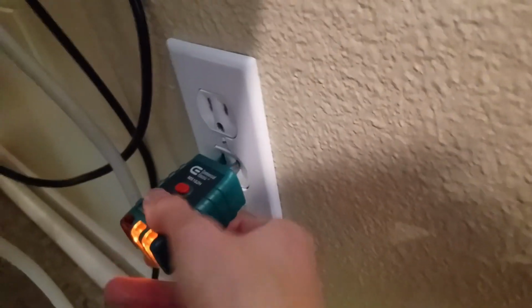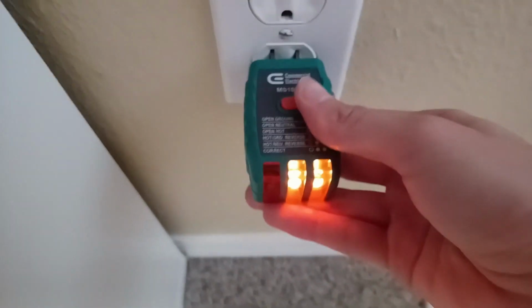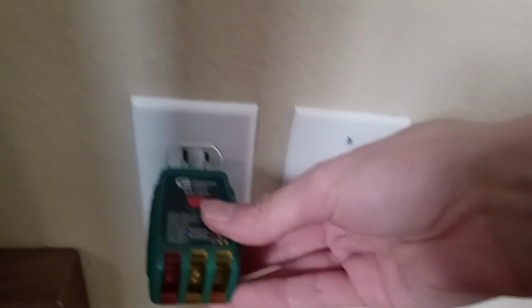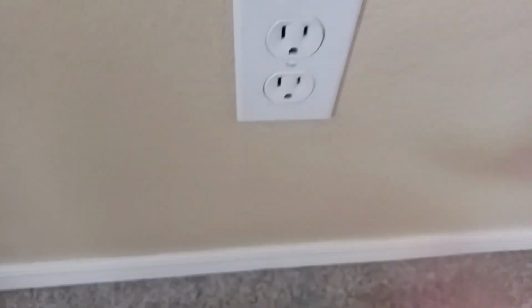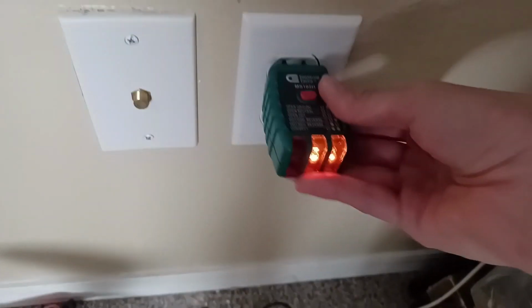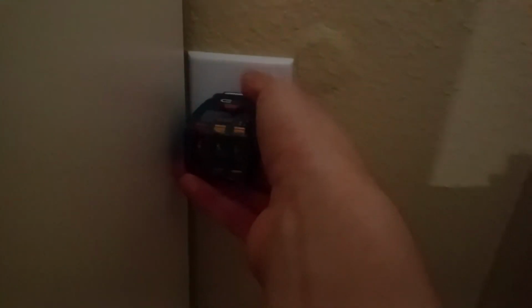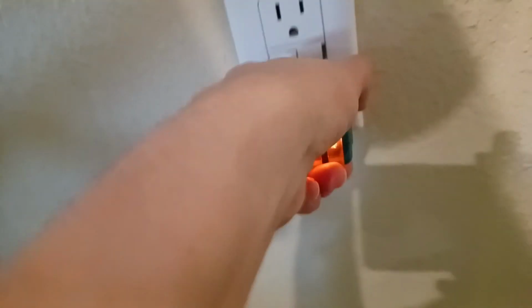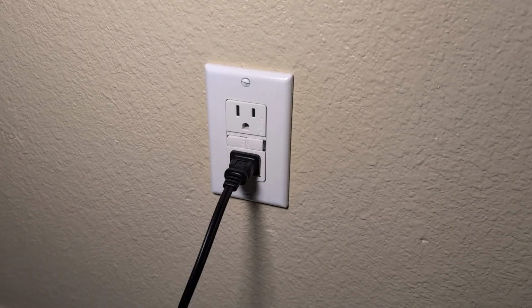This one. This one. This one. That one is good. This is good. Now it doesn't trip. And this one is good. Now if I trip it, it trips. And come back over here. If I reset it, power comes back. We're good now.